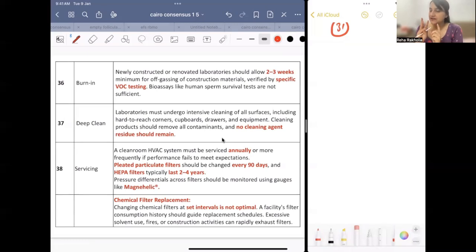We'll have to use three filters. What three filters will we use? Pleated particulate filter, which should be changed every 90 days, means 3 monthly. HEPA filter, which should be changed every 2 to 4 years. And the third filter is the carbon filter, that is called chemical filter, for which there is no set interval for change. We'll change it according to the environment.